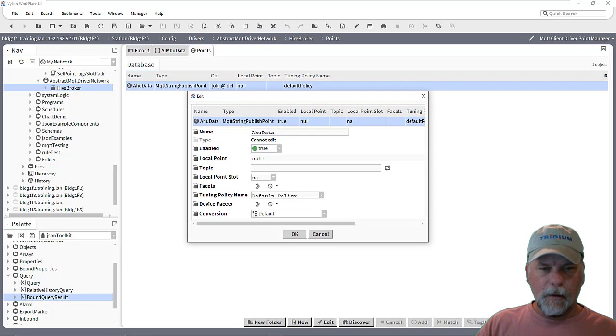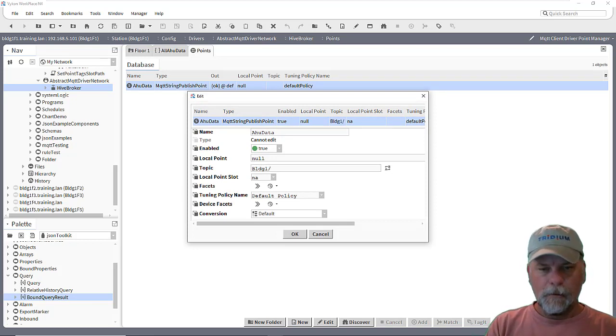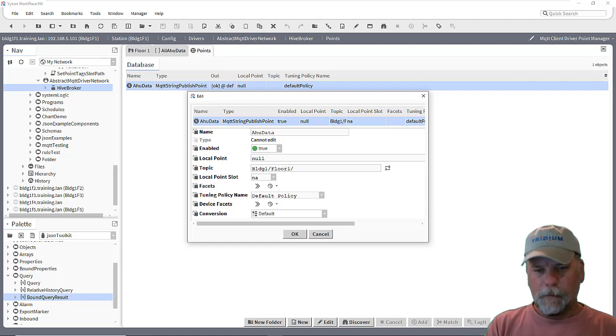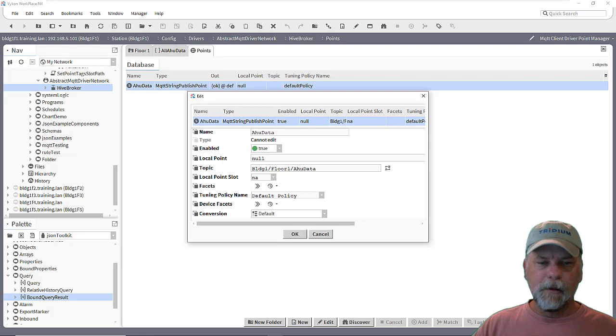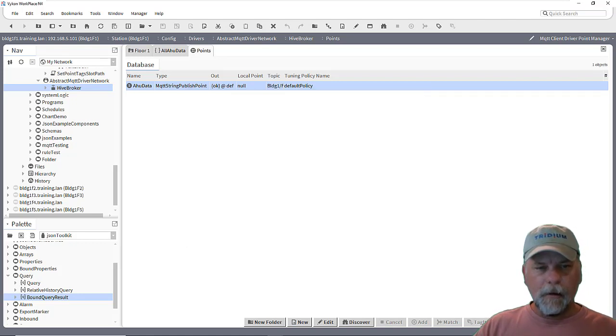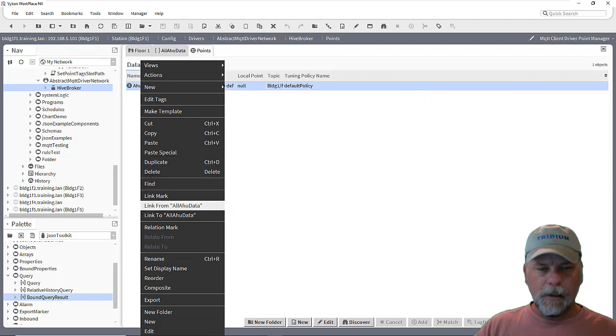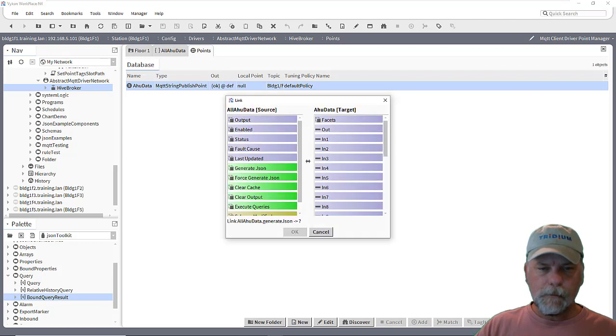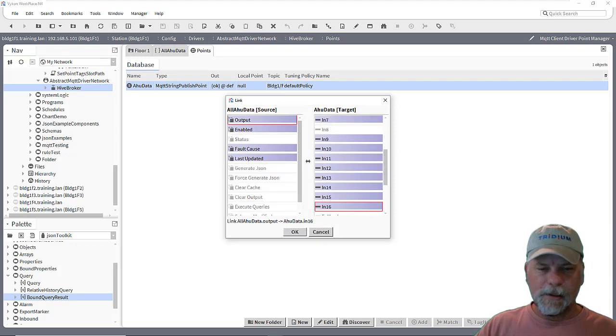And the idea here is that we can publish the point using a string publish point here. And in this case, we can set up a topic like building one, floor one, AHU data or something like that will be the topic. And we can link from the JSON schema component, take the output and link that into the In16 slot here.